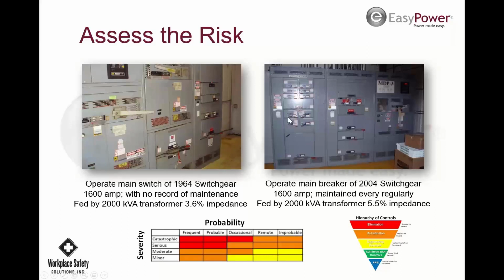And if I'm going to be operating a switch, like this one versus this one, we'll say this one right here versus this one, they're about the same position. I'm more comfortable operating this one than I will be on this one, because this main, I don't know if it's going to trip the way it's supposed to, and that's what's going to protect the line side of this switch. That's what doing an assessment's all about, just a risk assessment before your work. But that gives you an idea of some things to think about when you go.